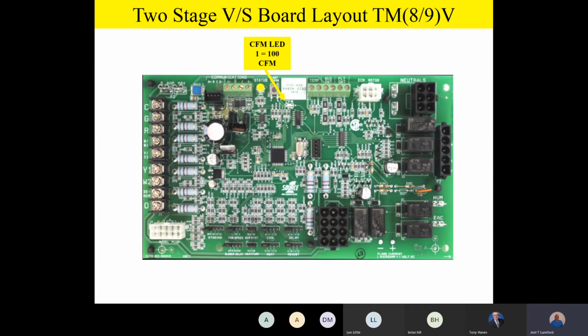If you see that CFM light, remember, team, anytime the fan is running, it's going to flash 1 time for every 100 CFM the fan is running. So what it does, it actually looks at the RPM of the fan and the airflow setup jumpers that we're going to talk about in a little bit, and then it extrapolates by the torque and the RPM and the rotor position of that fan. It extrapolates what our CFM is. So one flash equals 100 CFM anytime the fan is running.